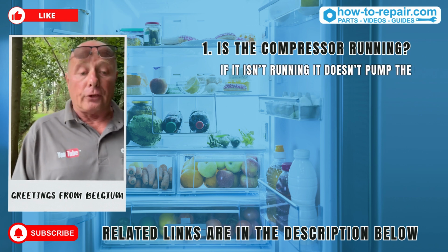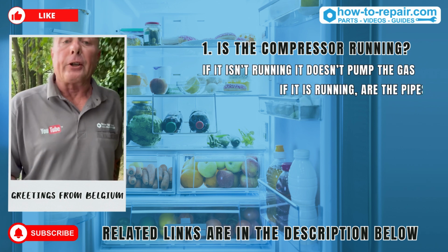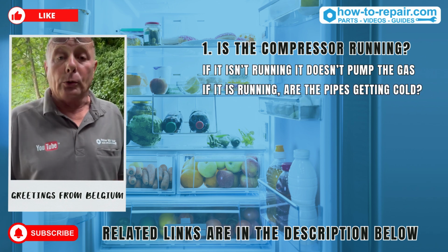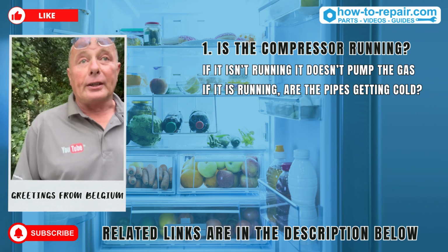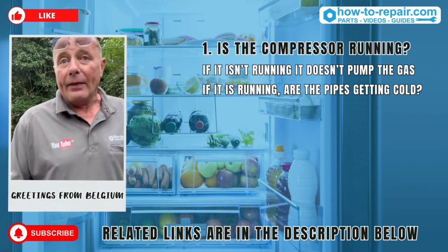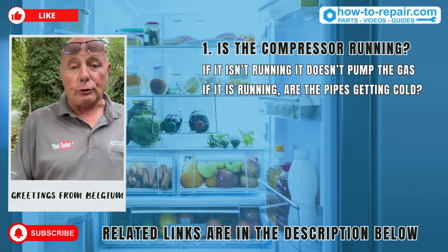If the compressor is not running, this means it's not pumping gas around the unit. If the compressor is running, then we need to know, are the pipes getting cold inside the freezer compartment? Because if they're not getting cold inside the freezer compartment, we could have a lack of gas in the system, and therefore it's running but not generating any cold temperatures.